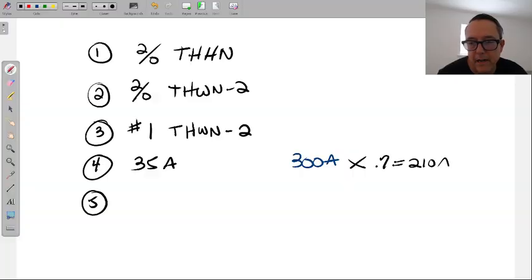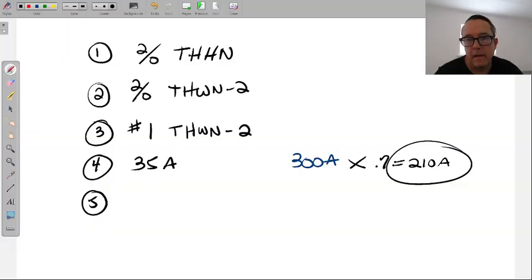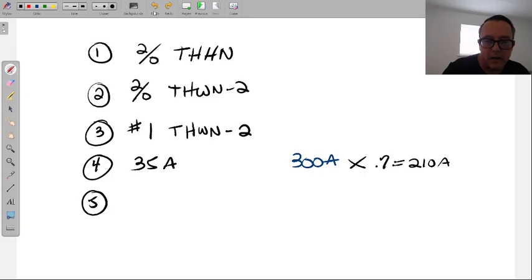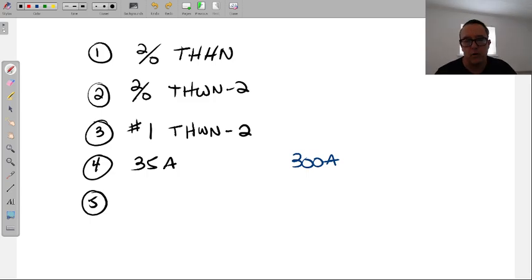So what you're telling me is simply that you did question 4 for me. That's the adjusted ampacity, 210. I need wires that can still cover 300 amps. So whatever wire you selected at 300 was too small. If you're going to multiply, you've got to pick a wire high enough that after you lose 30% of it, you can still cover 300.